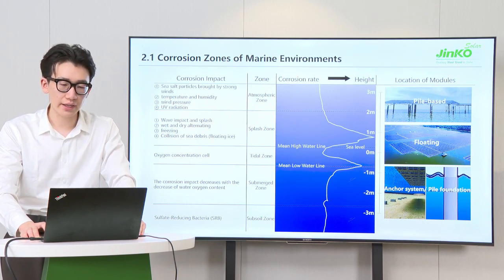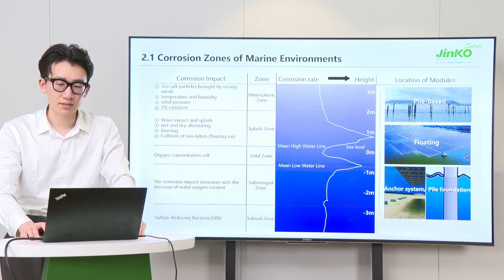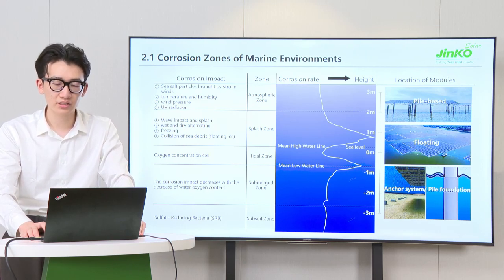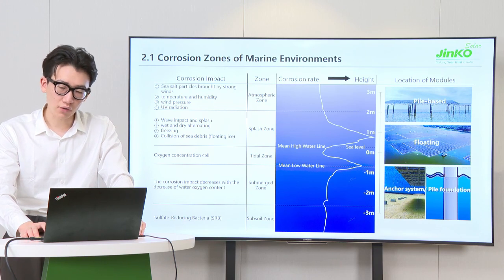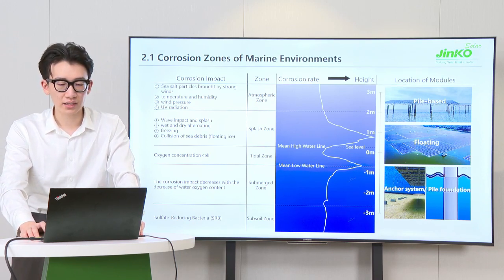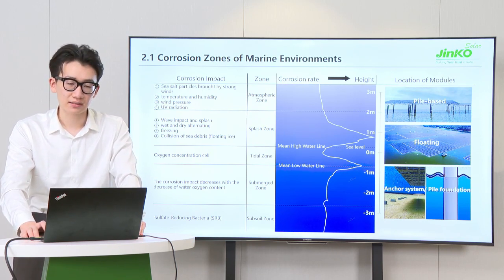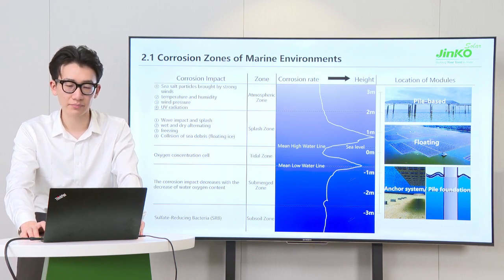Similarly, the influence of winds and UV radiation are also more severe. The splash zone is located at a distance of 0 to 2 meters from sea level, where modules are often impacted by waves. The surface alternates between dry and wet conditions, and with sufficient water and oxygen supply, it makes this the most severely corroded area in the marine environment. The tidal zone is located between the mean high-water line and the mean low-water line, which is protected as a cathode area of an oxygen concentration cell and has a low corrosion rate. However, there is a risk of marine biofouling in this area.